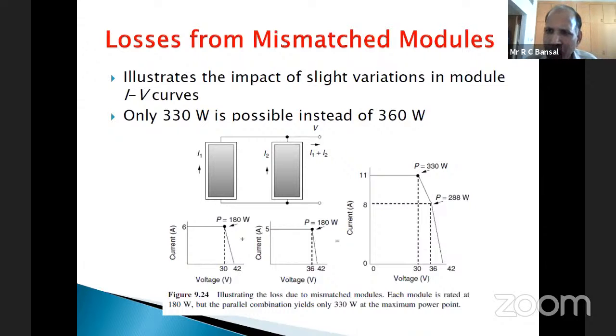You have to see that its voltage and current rating should also match. The previous modules may have had a current rating of 6 amps with a voltage rating of 30, giving a power rating of voltage multiplied by current: 6 into 30 equals 180 watt.